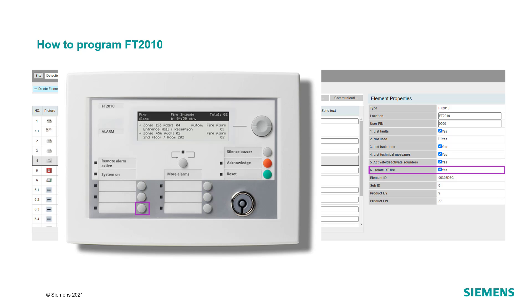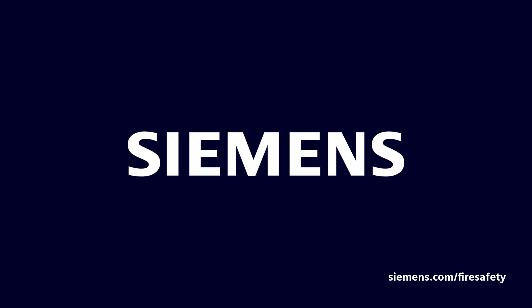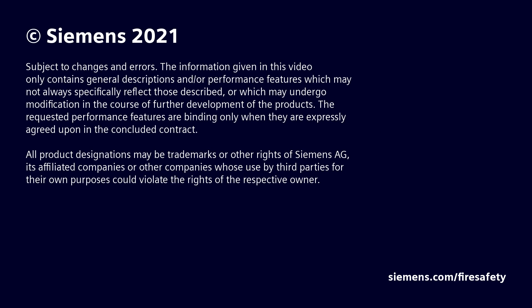The last configuration option is the function Isolate RT Fire, which means that, if it is activated, the user can disable the outputs configured as remote transmission fire with the button on the lower left. Please note that the key switch needs to be activated in order to use any of the program functions. Finally, apply the configuration to the panel and test the application.